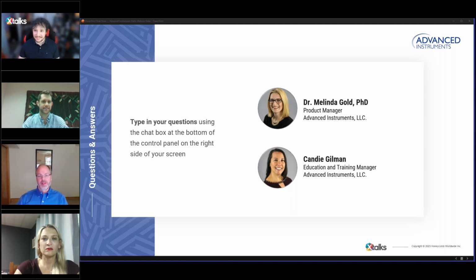There are some studies that have been conducted. Mostly, one study has been conducted by the Euramet organization. Euramet is the Association of the European National Metrology Institutes, and they looked at users' micropipettes and tried to see what is an achievable error tolerance. And if I'm not mistaken, the results can be interpreted in a way that about a 2% systematic error and a 1% random error is a good starting point, and it's typically achievable by users. And I believe these are also the recommended tolerances in ASTM E1154. So that might be a good starting point, but definitely your process tolerances, as Ryan mentioned, are the determining factor.